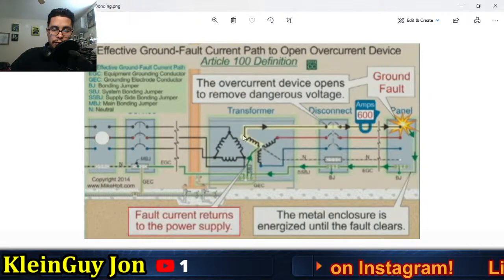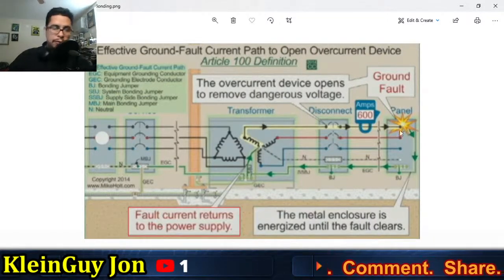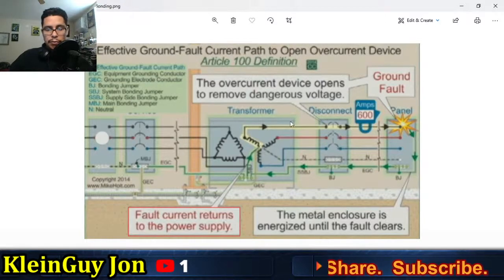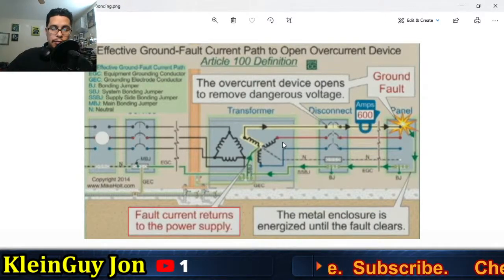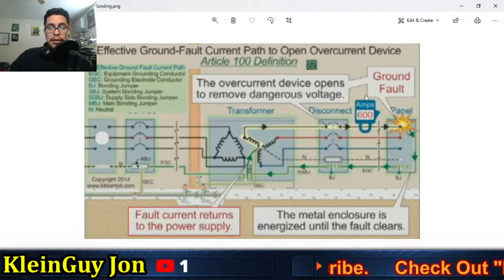You remove voltage. The breaker trips, the voltage is removed safely. And what do you do? You troubleshoot, fix whatever is causing the fault, repair it, and the breaker will have to be reset. Turn it back on, and then everything is back up and running again. But this is an example of an effective ground fault current path.